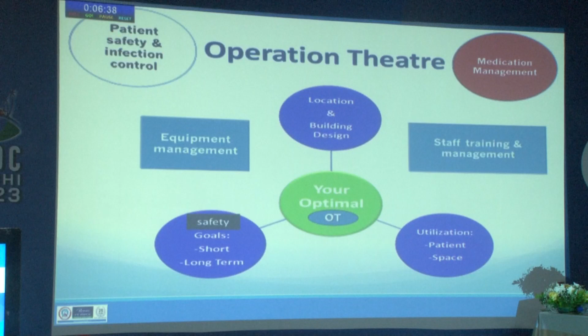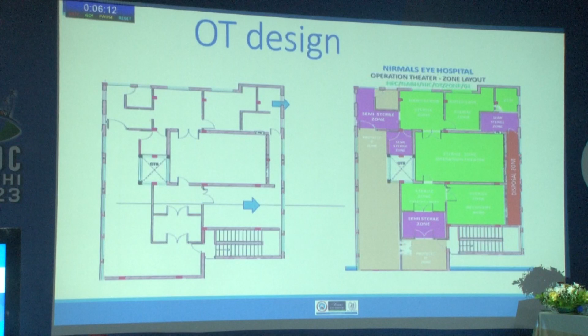So as I said earlier, four well-defined zones are important, and the ideal design is that the green area is the sterile area, then the support areas have to be semi-sterile, and then we have the administrative areas or the entry zones, and then finally the disposal corridor where the infected or soiled linen and instruments are all taken care of, washed and reused or disposed. So basically you have to divide the space into cleaning, disinfection and sterilization areas, but ensure this important principle, unidirectional flow, is followed. So OT walls, these are some of the oft-repeated questions.